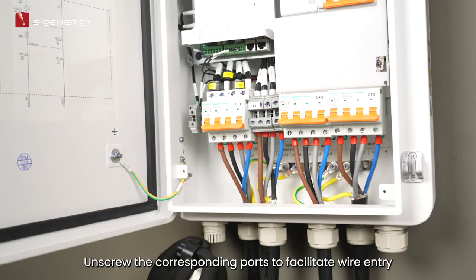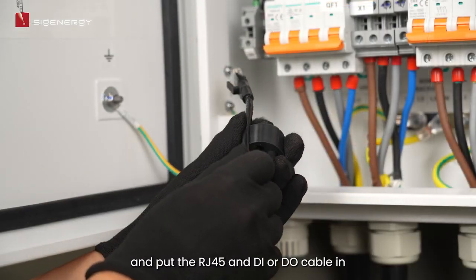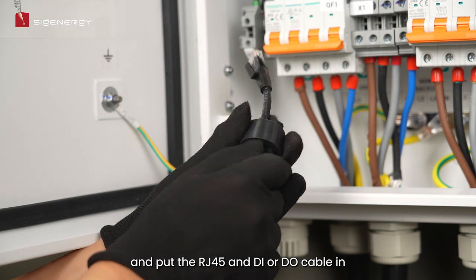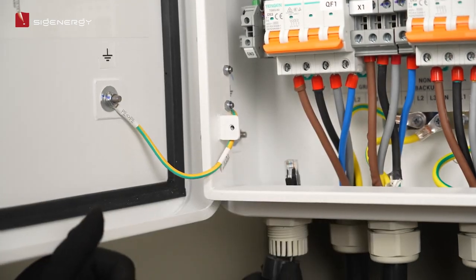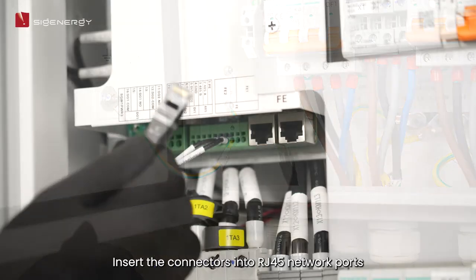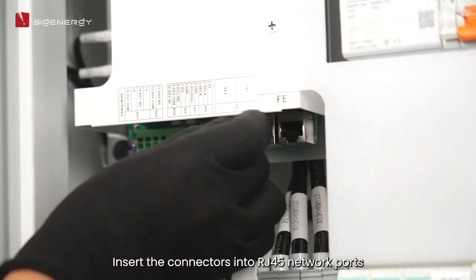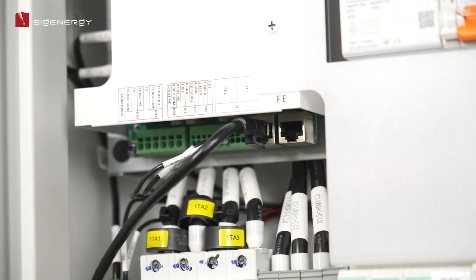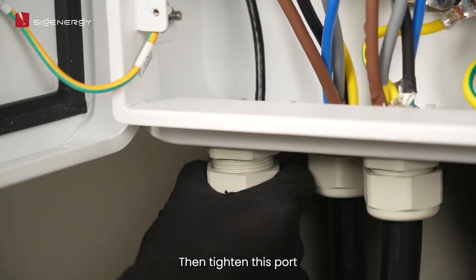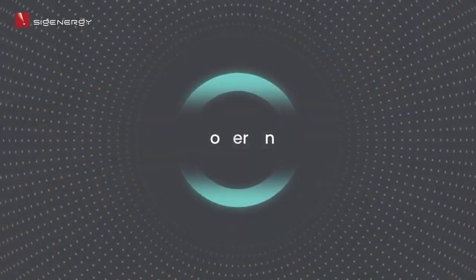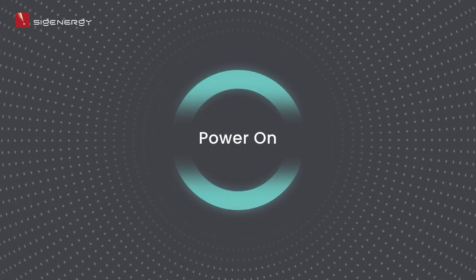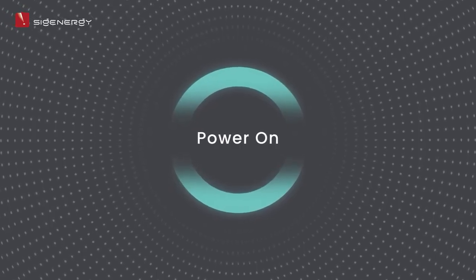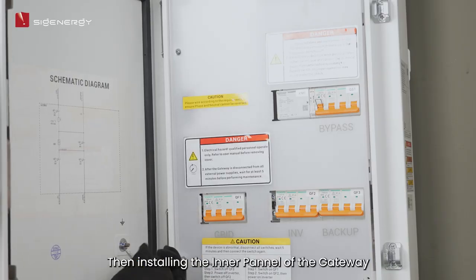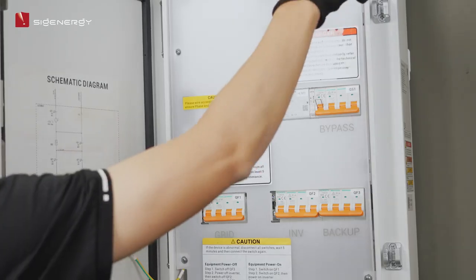Unscrew the corresponding ports to facilitate wire entry. You can disassemble the terminal and put the RJ45 and DI or DO cable in. Insert the connectors into the RJ45 network ports. Then tighten this port. Then install the inner panel of the gateway.